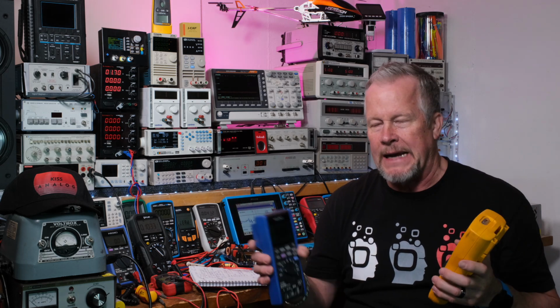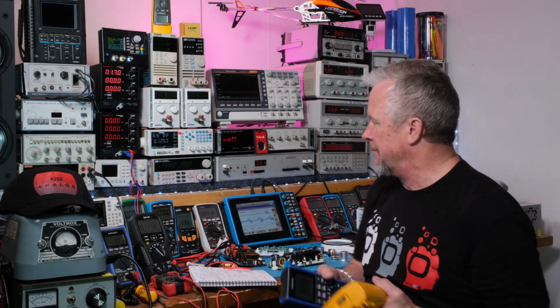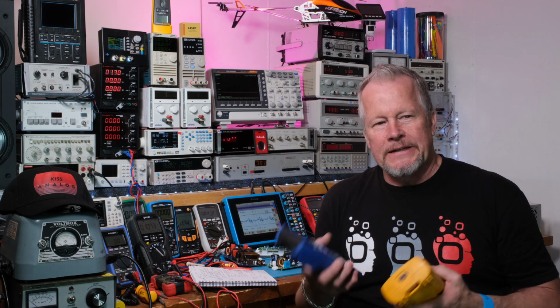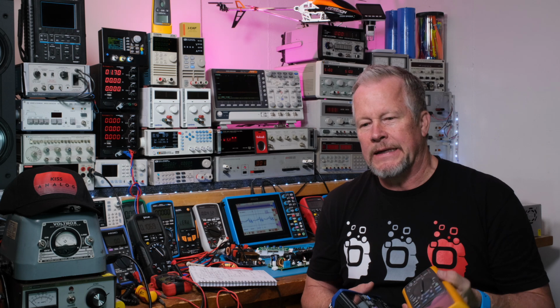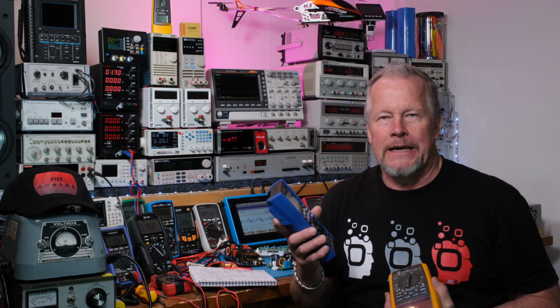It can help you troubleshoot those noisy AC measurements. The other thing, a lot of 6,000 count meters have max and min measurements, right? Well, I was talking to a guy the other day, and he had a current probe, and I was using my Redfish current probe to take a peak inrush current measurement. He goes, oh, you can use my current clamp as well. I said, well, no, that takes maximum. He goes, well, that's the same thing. I said, no, it's not. Max measurements are usually around 100 milliseconds. So motors, when they inrush and start up, usually settle down after 100 milliseconds, so it'll capture something like that.